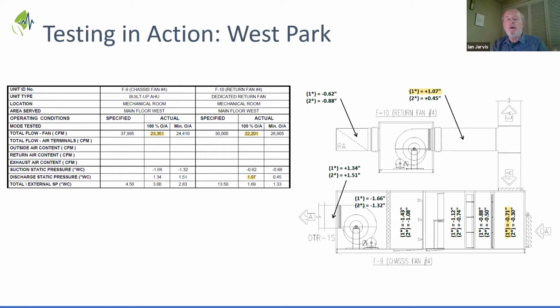And also in the minimum outside air, which is how the systems would run right through the hot weather in the summer and right through the cold weather in the winter. So you measure in those two scenarios because they tell you quite different and complementary things. When we look at the 100% outside air scenario here, there's a few things. One is that the total airflow is 23,351, sorry, on the supply side versus the 38,000 it should have been.